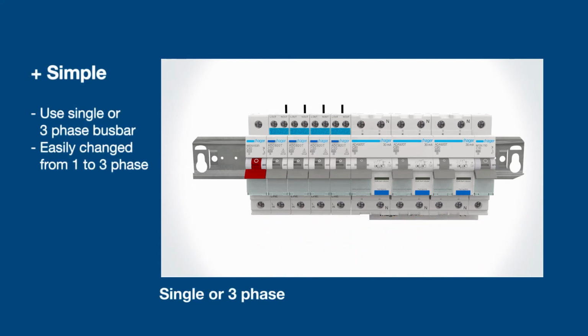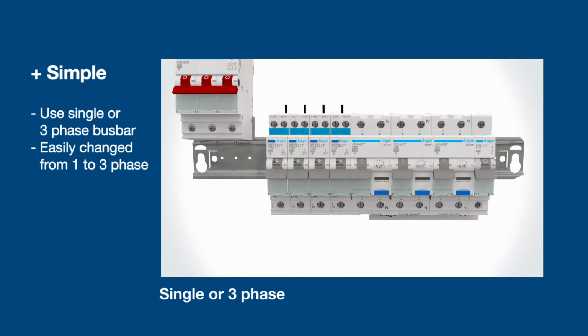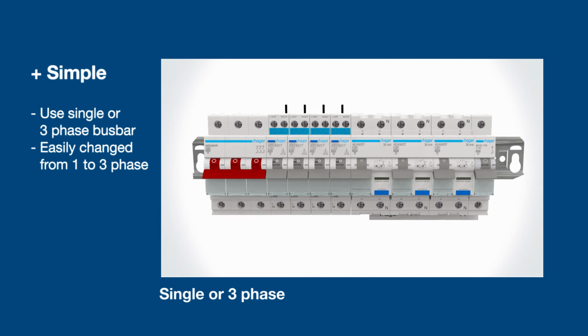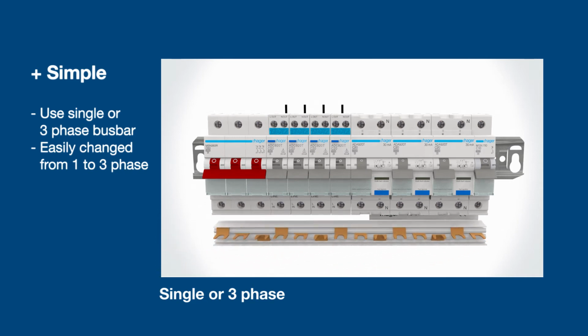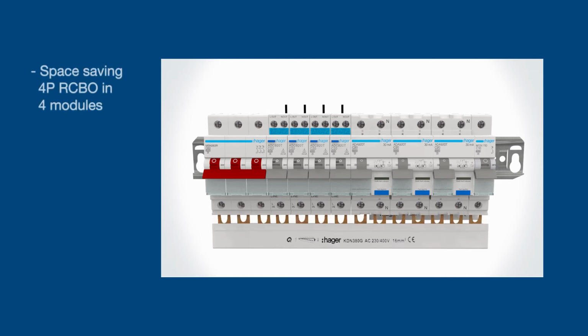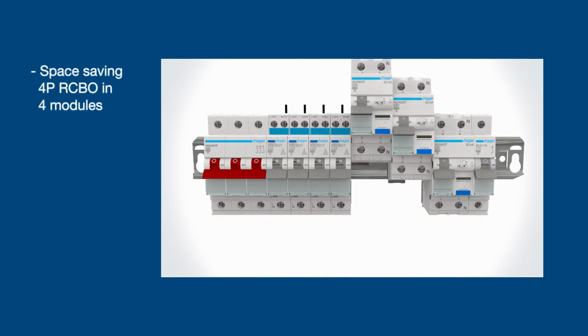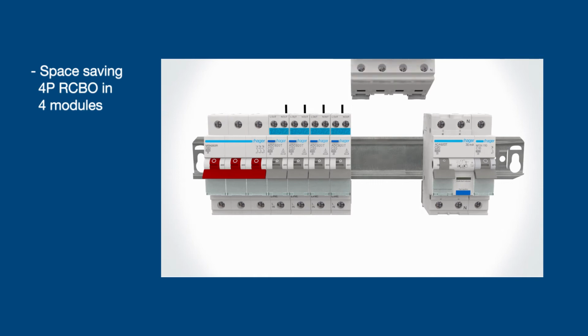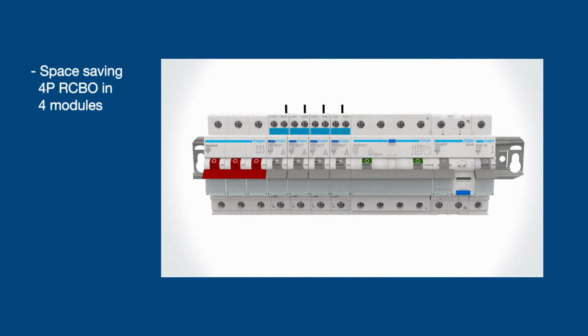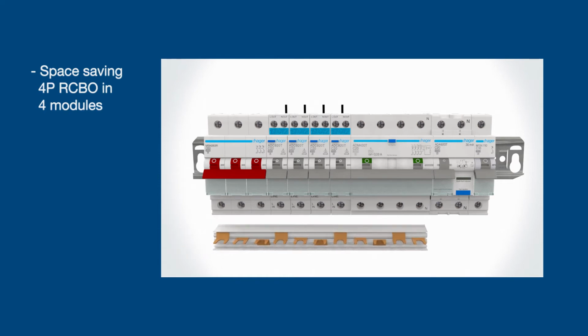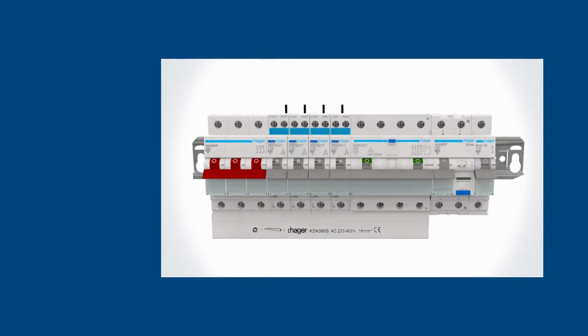If a 3-phase is required, or if upgrading from single to 3-phase, simply install your preferred main 3-phase incomer and utilize the 3-phase busbar for an equally fast and efficient connection. Our 3-phase RCBOs are only 4 modules and fit on the busbar. To feed the neutral in, the terminal can accommodate a cable up to 25 square millimeters.